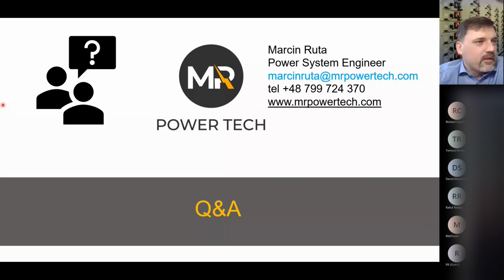What else we have? What about arc flash releasing duct located on the switchgear? I assume that you mean that there is an arc flash venting system or arc flash release system. So when you design the switchgear, like low voltage or medium voltage, part of the hardware design and simulation is that you create a part of the switchgear able to open, or sometimes there is some kind of arc coolers, how you can call it. It is venting back the pressure and generally the energy pressure outside the switchgear. It might be outside of the building, it might be to the cable chamber. Generally depends what you have possible in your switchgear substation. So yes, it is part of the internal arc classification design, it's part of arc rated design.